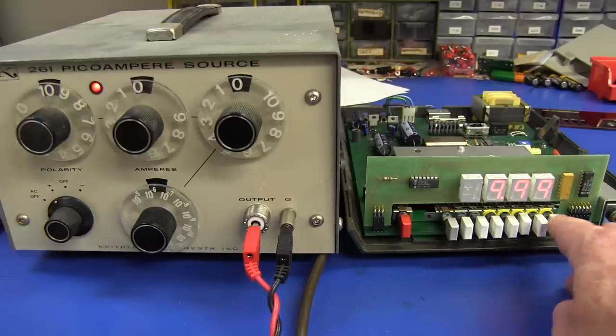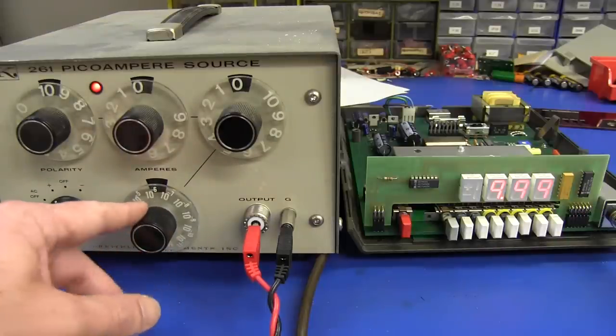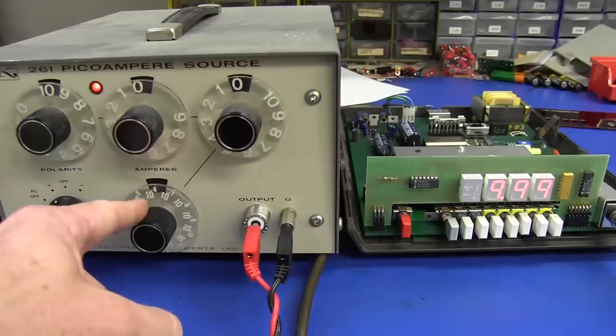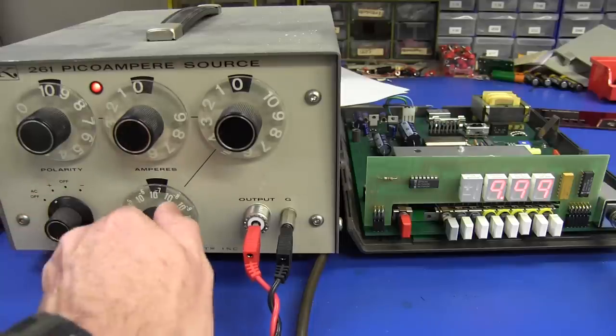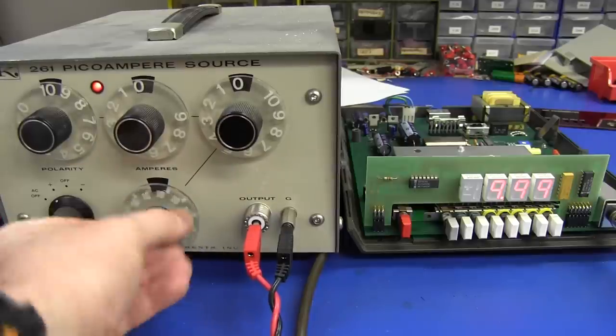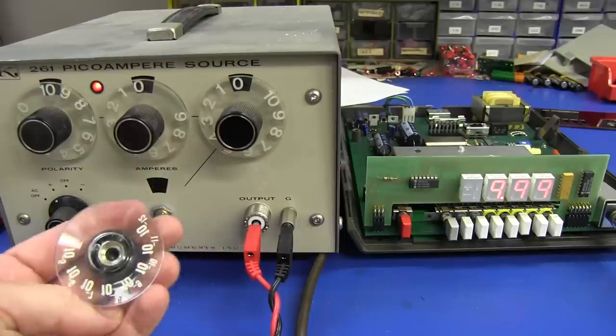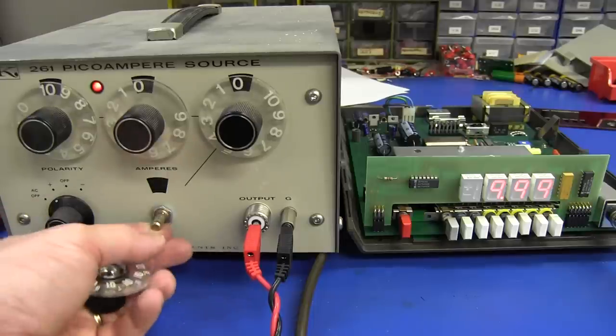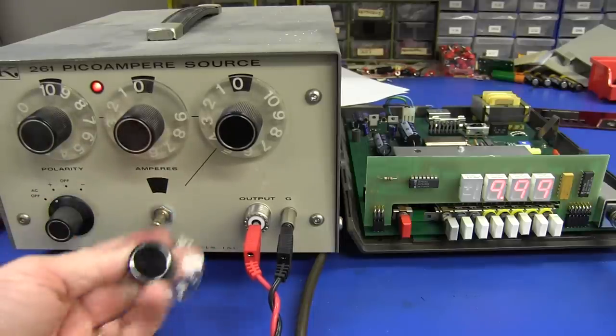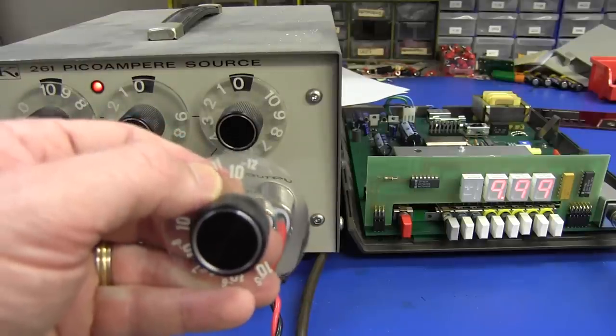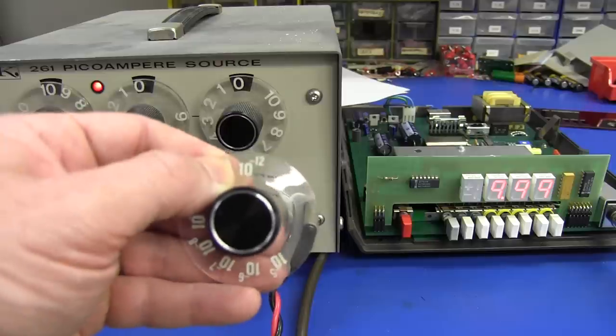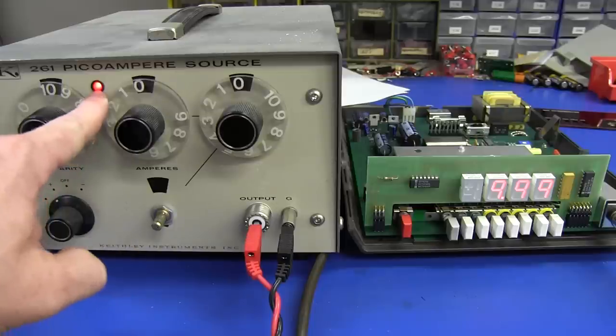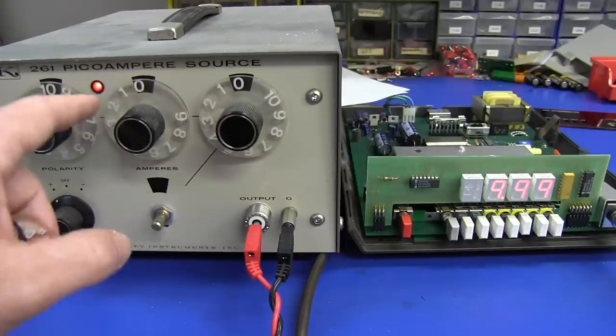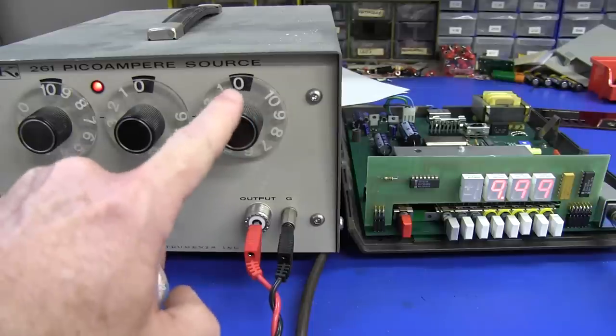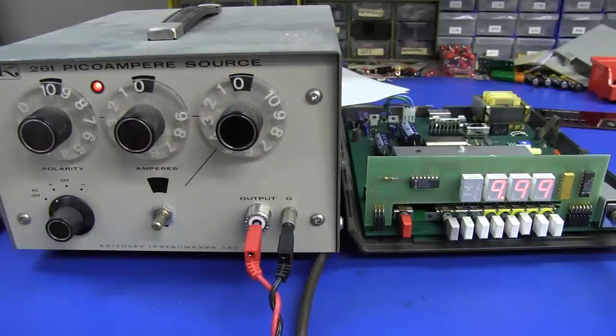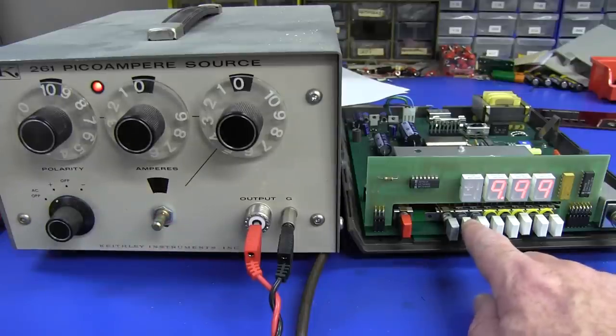So if we need to go to higher currents for the milliamp ranges, this can't do that. This starts from 10 to the minus 5, so it starts from 10 microamps full scale down to femtoamps. It can go, oh, this knob is dicky. It's completely dodgy. Ah, there we go. Nah, ruined. Got to really tighten it, maybe flatten the shaft out on this thing. But anyway, trust me, this thing does go down to a minimum of 10 to the power of minus 12, i.e. 10 picoamps full scale. And you can adjust that because this shows where the decimal point is. Then we're talking about 10 femtoamps resolution on this thing. It's really quite good and more than good enough for testing the range of this thing, which is 1 nanoamp full scale.